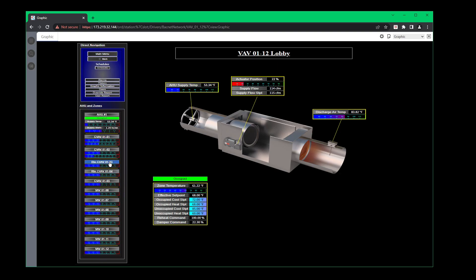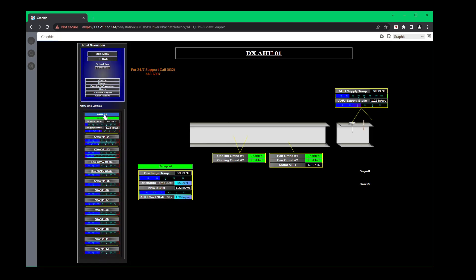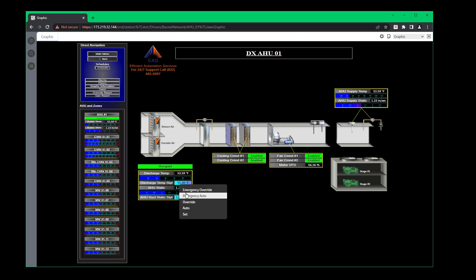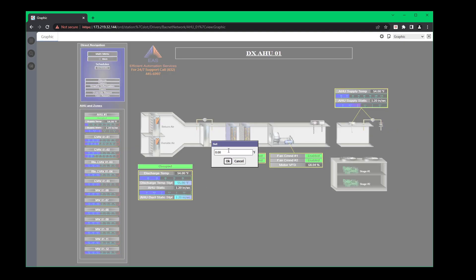If you want to go back or if you just want to jump to a box, you can do that from right here on the left. Same thing, you can click on this and this will bring you to the air handler. So let's say the building is getting warm and you're trying to figure out what's going on. One is you want to make sure that you have your cooling commands. So here's your cooling commands that are enabled and what these are doing is this is trying to maintain this discharge air temp set point right here of 55 which is adjustable just like your heating and cooling set points on your VAV. You'd right click, go to set, always use set and then you can make your adjustments. So let's say you wanted to make it 60 degrees, you can.